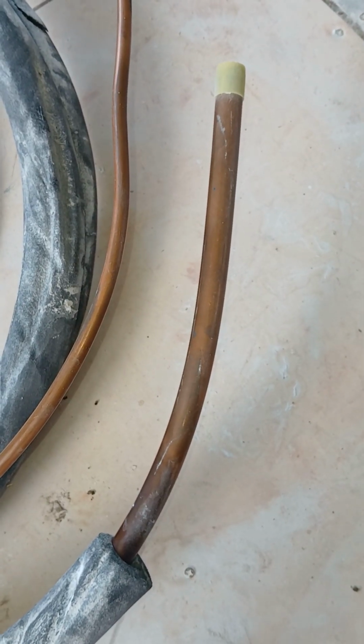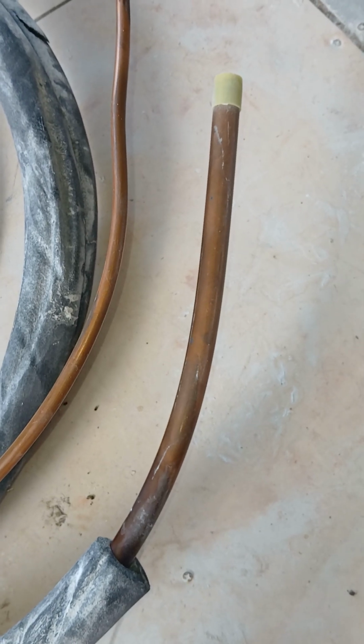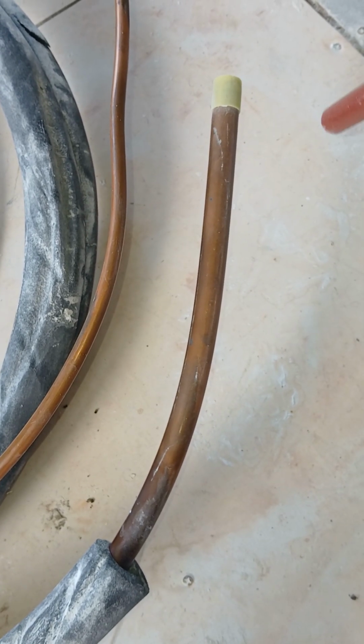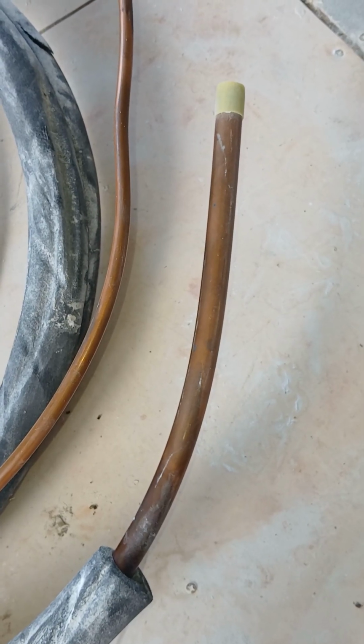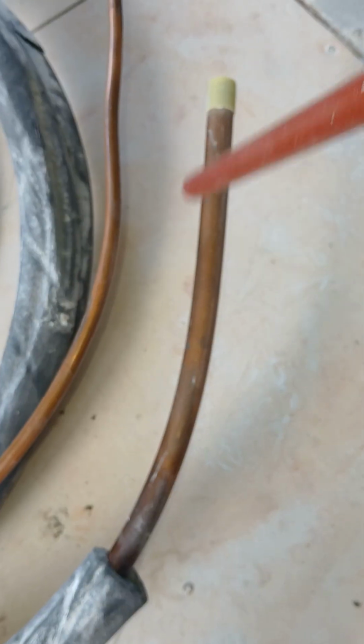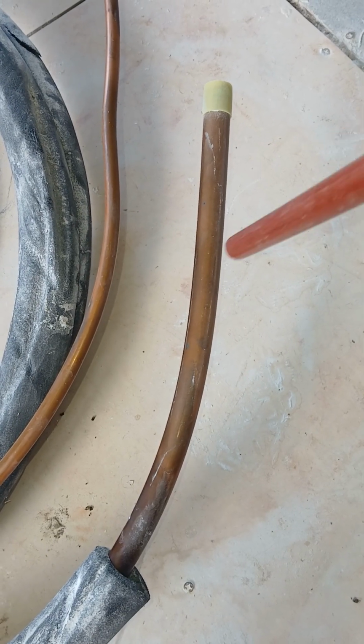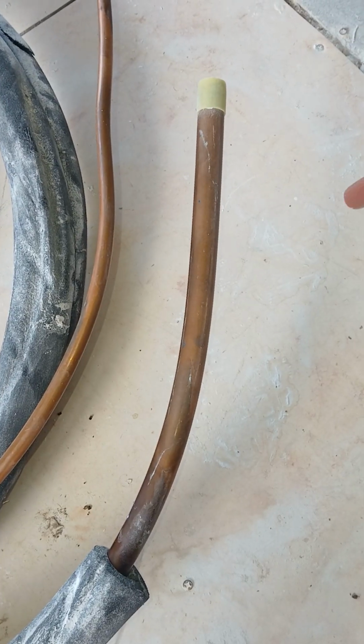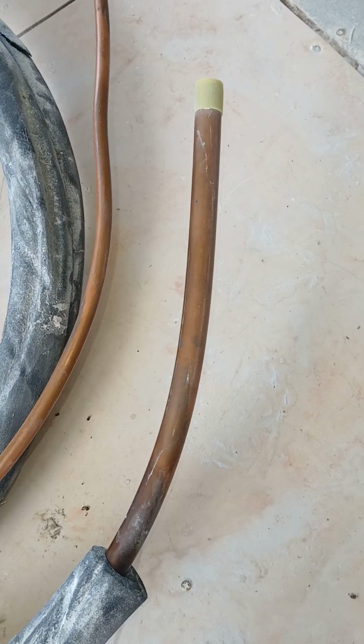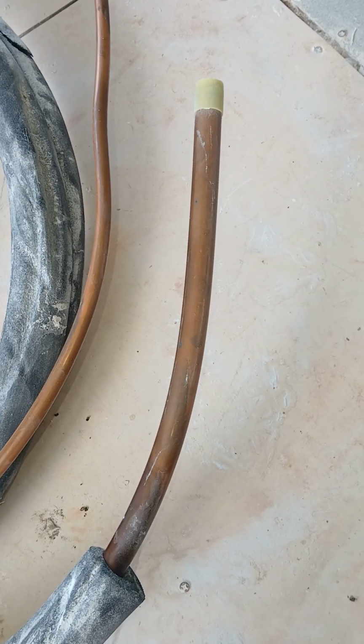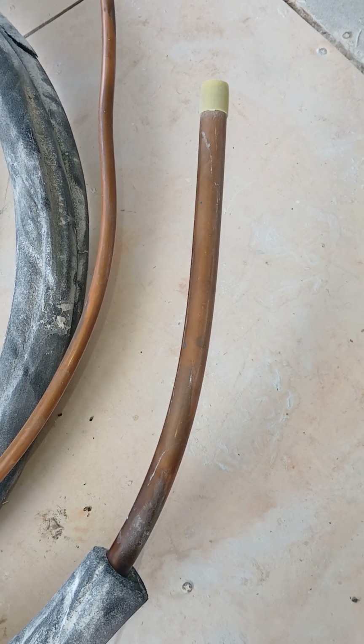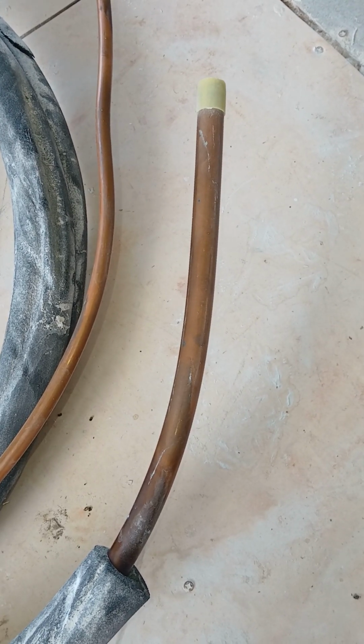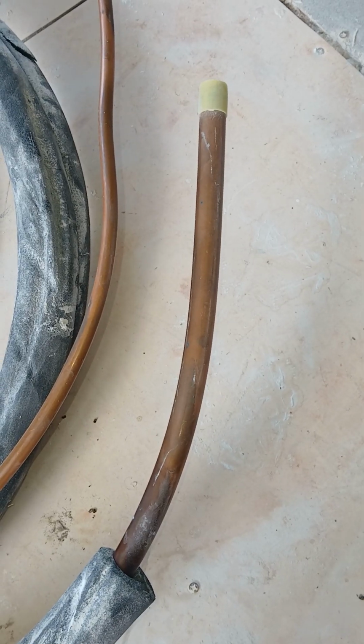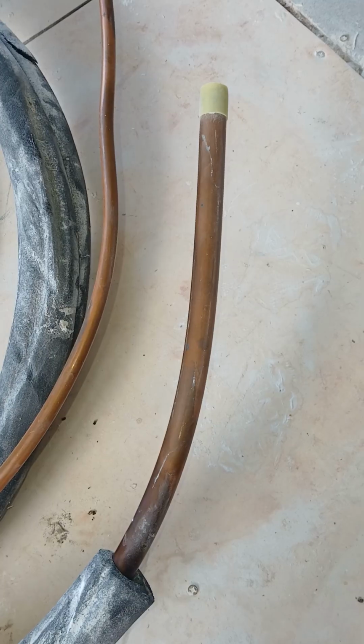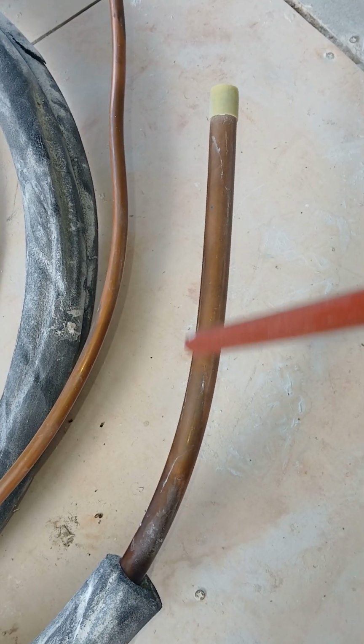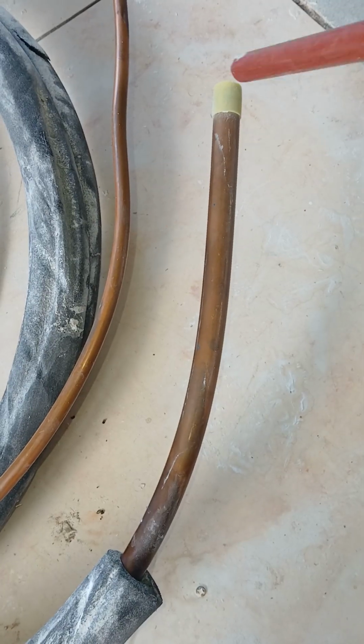If your refrigerant leaks out, you may have to call a technician to repair it, and then they would have to pull a vacuum. So it can be detailed. If you're crawling under the house and you see these lines, or if you have somebody driving a nail or a screw, just be careful you don't puncture these. If you do puncture them, be sure to get away from it till it depressurizes, because you're not supposed to release the refrigerant into the air. Not only that, the refrigerant boils at some minus 40 some odd degrees, and it can hit your skin, and it's not going to be good. So just be careful that you don't break these lines.